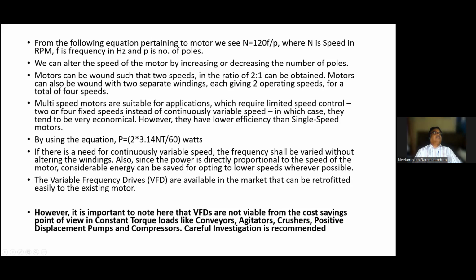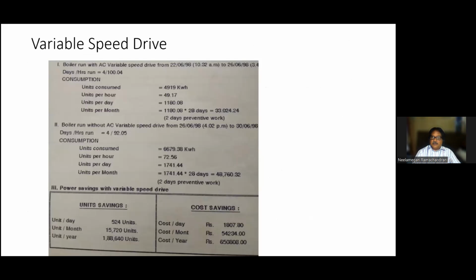So this is a simple boiler in '96. We changed the ID fan and FD fan: instead of damper control of the incoming air, we fitted a drive, and this was the cost saving we had. And to all plant engineers, my request on energy conservation and efficiency: instead of projecting and calculating, it's better to connect an analyzer and see for 1 week without the VFD drive. Then after the improvement, we connect the power analyzer and check all the parameters and the units also. Like this, we can easily point out the units saved.